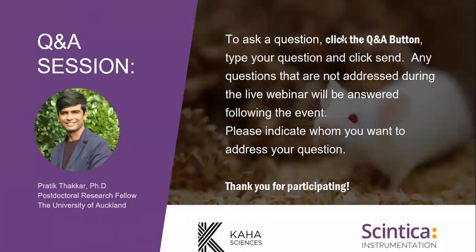First question we got is, were the telemeters checked after removal from the animal to ensure that they were still recording accurately? For example, any calibration checks or anything like that? Right. So this is a great question. Yes, after I remove the telemeters, once the protocol finishes and after euthanasia of the animal, I have to check the offset of each telemeter.